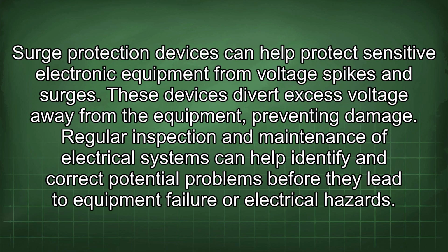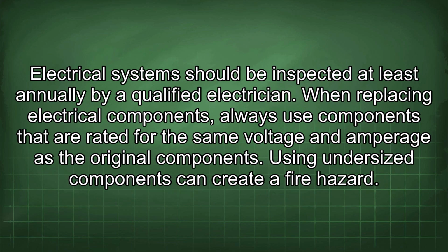Surge protection devices can help protect sensitive electronic equipment from voltage spikes and surges. These devices divert excess voltage away from the equipment, preventing damage. Regular inspection and maintenance of electrical systems can help identify and correct potential problems before they lead to equipment failure or electrical hazards. Electrical systems should be inspected at least annually by a qualified electrician. When replacing electrical components, always use components that are rated for the same voltage and amperage as the original components.